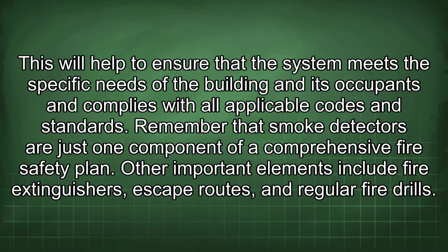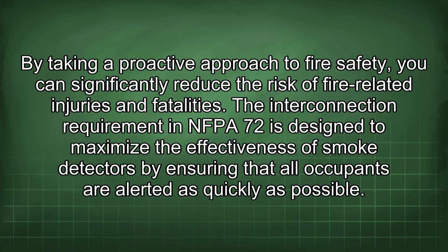Remember that smoke detectors are just one component of a comprehensive fire safety plan. Other important elements include fire extinguishers, escape routes, and regular fire drills. By taking a proactive approach to fire safety, you can significantly reduce the risk of fire-related injuries and fatalities. The interconnection requirement in NFPA 72 is designed to maximize the effectiveness of smoke detectors by ensuring that all occupants are alerted as quickly as possible.